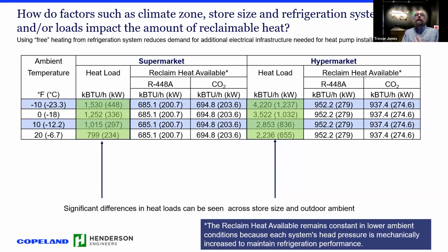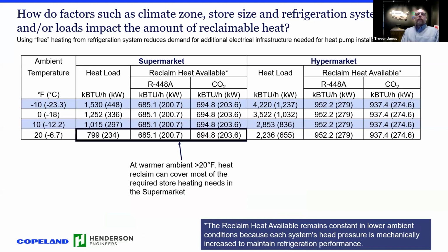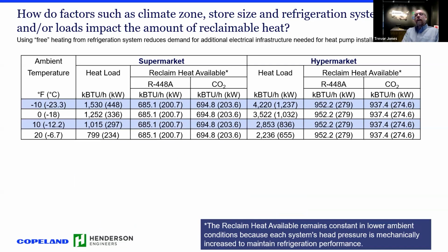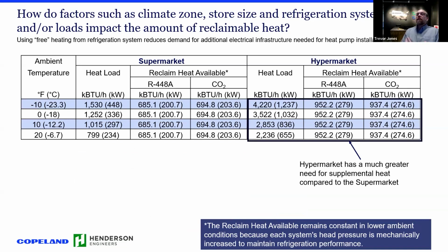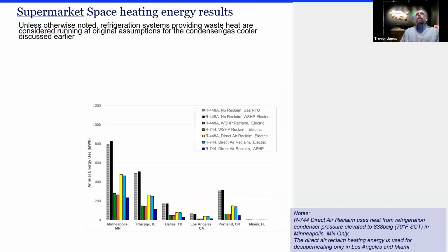Also, the hypermarket has a significantly larger heating load. For the supermarket, around 20 degrees, the amount of heat that is available from the refrigeration system is really close to the heating load. With the hypermarket, we're only at best half at 20 degrees. So 20 degrees was the break-even point for the supermarket. Much higher temperatures were needed at the hypermarket. That was into about the low 40s before the hypermarket was coming close.